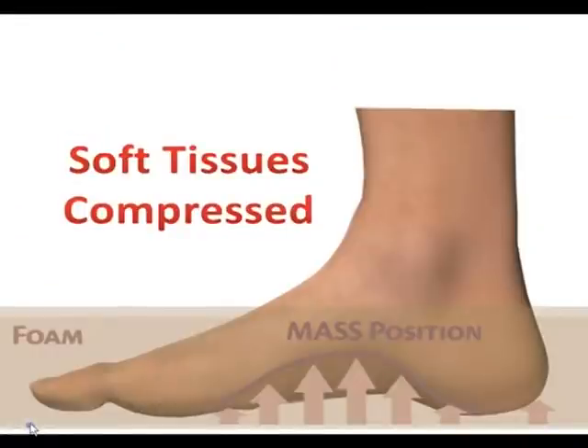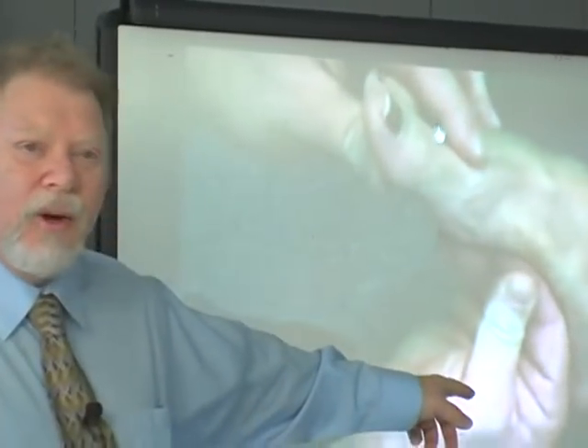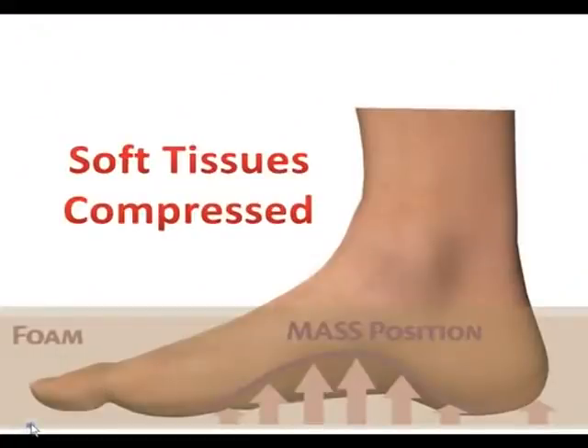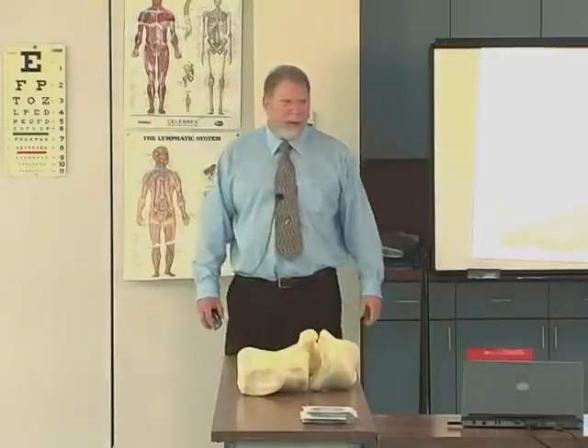The other thing missed was soft tissue compression. Hang the foot out in space and all the soft tissues round out — you end up with about a quarter of an inch too much soft tissue. But when they wear the orthotic, it will compress the soft tissues, and you lose a quarter of an inch of orthotic arch height. That's massive. So you want a material that when doing the cast will evenly compress all the soft tissues. We experimented with various materials and found we needed to use our own foam. Biofoam is a 2.25 PSI foam — we had to drop it to 1.75 PSI to make it work, going in at this depth of three full inches, to make it tolerable by the human body. So we had to reinvent the foam casting box in its density only, to get soft tissue compression.